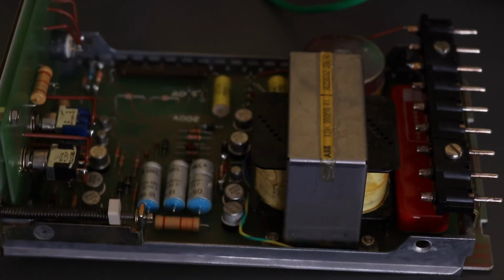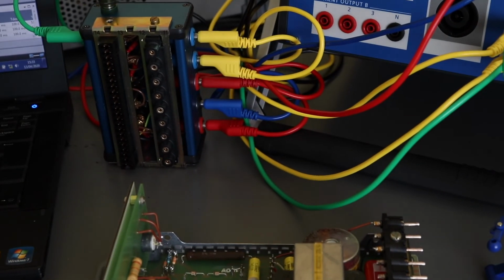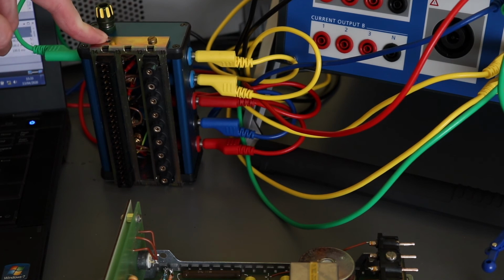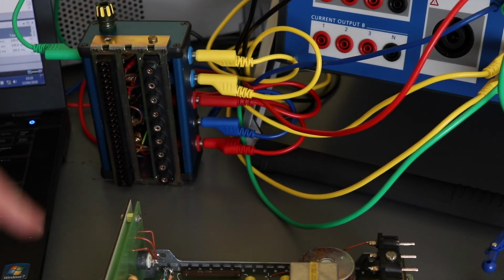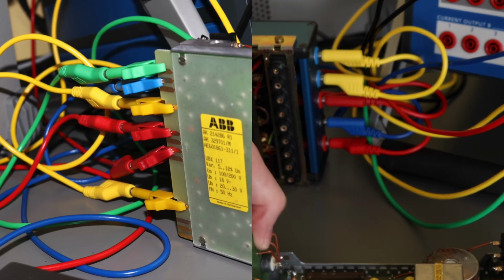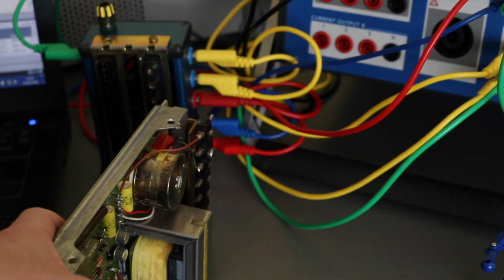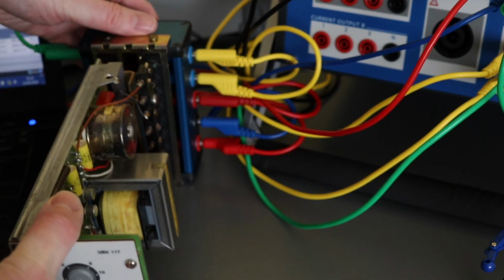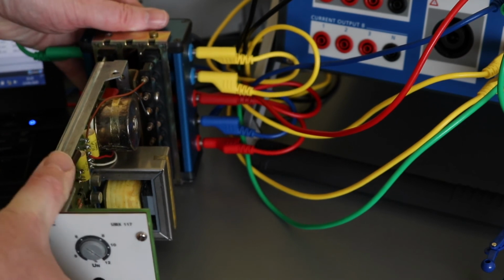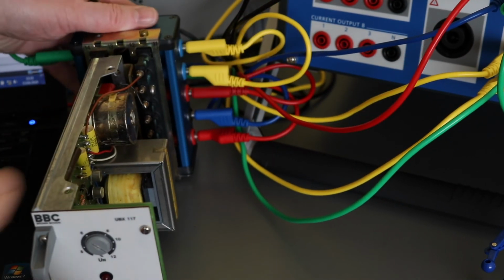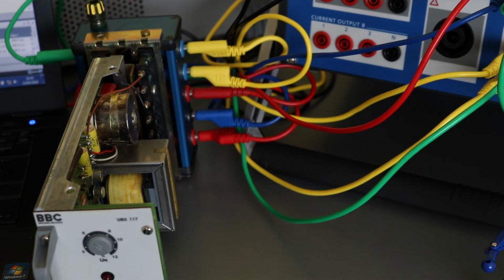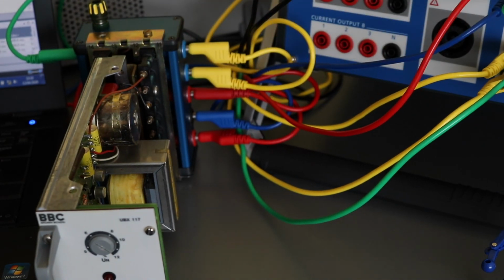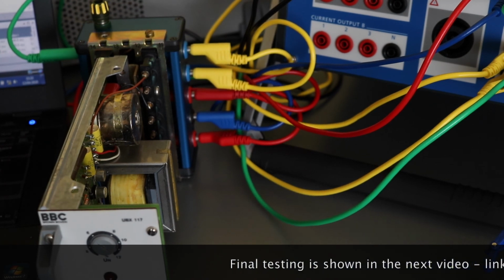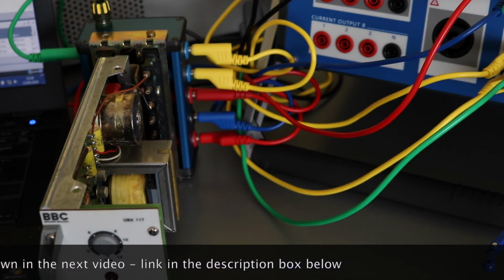And then you'll also notice, go up a little bit, and I actually built up here a little adapter box to plug the relays into to make it a bit better. It was a bit better than the crocodile clips that I was using for the previous connections. So in order to get the relay plugged in, I just slide him straight in like that, and then the connections are all made, and then I'm on standard banana leads through to the injection test set, same power supply behind at the back to provide the tripping voltage. So we'll reset up and we'll give this a final test.